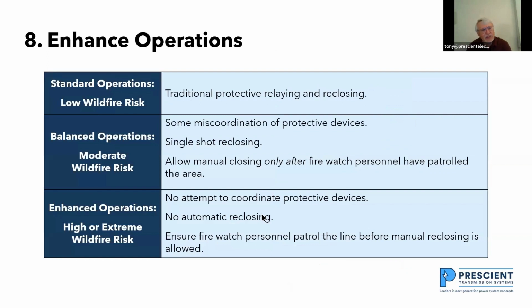So I'm looking at things like this. You're going to take all this together, and you're going to have standard operating modes, balanced operating modes, and enhanced operating modes. With the standard operating modes, you're going to have traditional protective relaying and reclosing practices. These are set up so that I optimize my interruption frequencies, my interruption duration, and those key indicators I'm looking at. In balanced operation, I'm going to allow miscoordination of some devices. I will allow single shot reclosing, but I'll only allow manual reclosing after a fire watch patrols the line and determines there's no fire in the area.